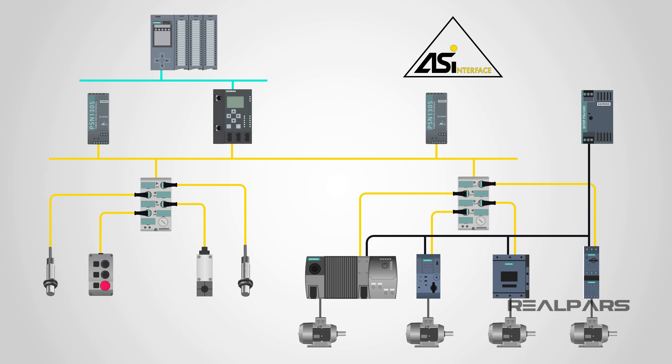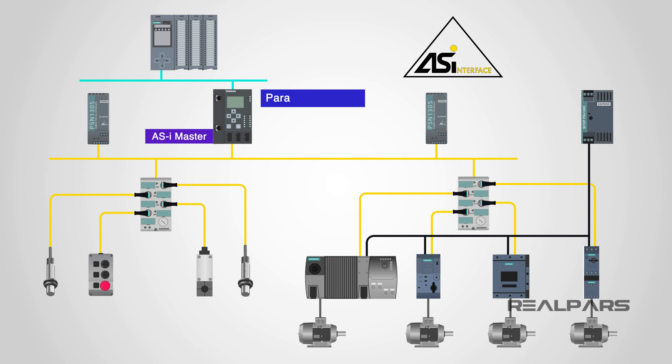A system built using the AS Interface typically has three components. Firstly, there is the AS Interface master — the head of the network. The AS Interface master provides the connection to the higher level control system. It organizes all of the data traffic on the line and is responsible for parameter setting, diagnostics, and monitoring.